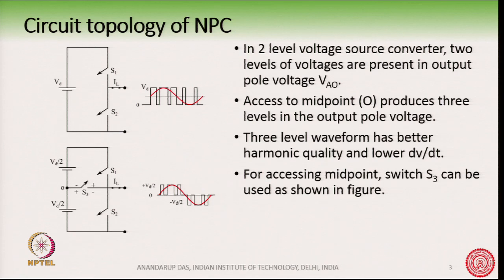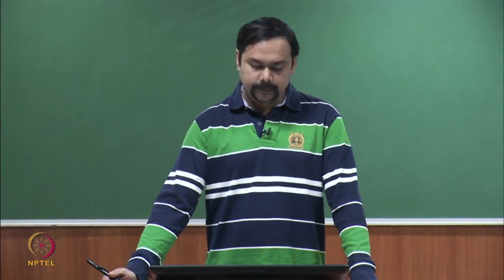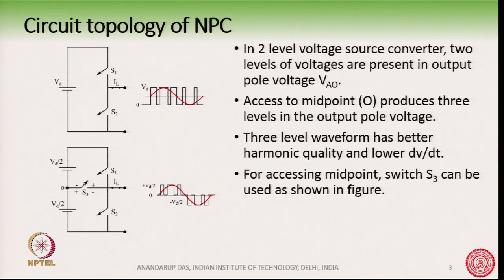there are several drawbacks which we have said earlier, and that is why some people go for a multi-level converter in its design. One drawback is that we need a high switching frequency of the switches, so that the size of the filter is reduced. And if you do not have a filter, then sometimes the dV/dt on the motor, for example when this converter is driving a motor, can be quite high, especially with a long cable.